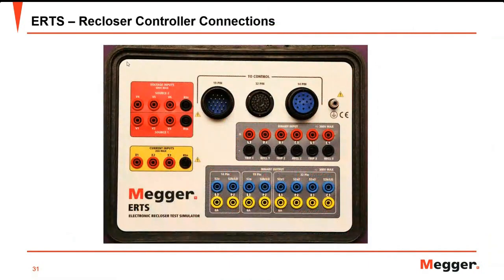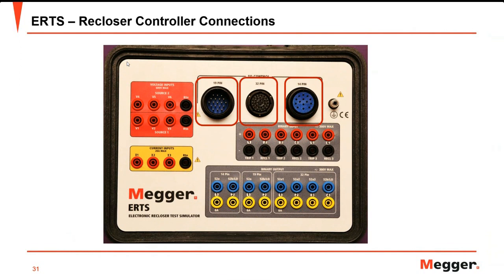Taking a closer look at the ERTS: three different multi-pin connectors provide flexibility for the different types of reclosers commonly found in the market. To simulate and test we have the 19-pin connector, the 32-pin connector, and the 14-pin connector. The Megger relay test units provide individual test currents and voltage through the interface unit and monitor the individual trip and reclose circuits from the simulator.